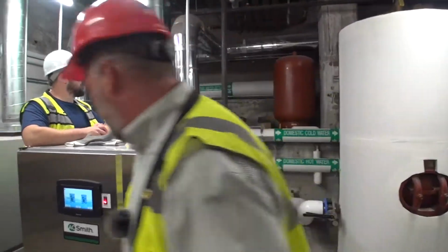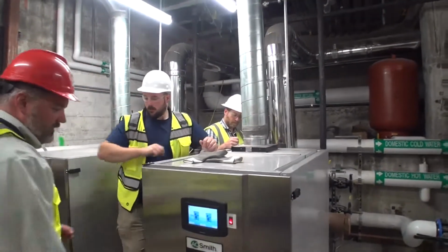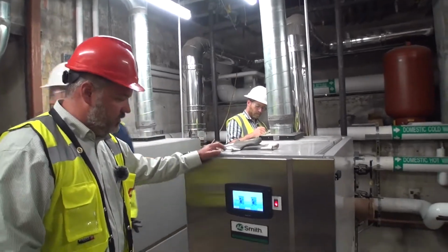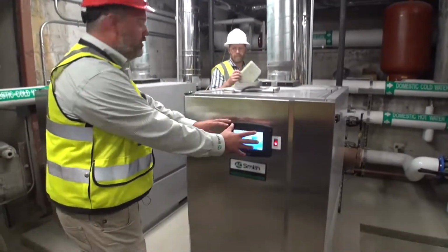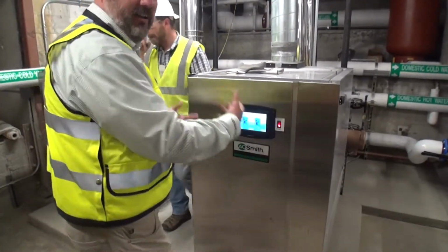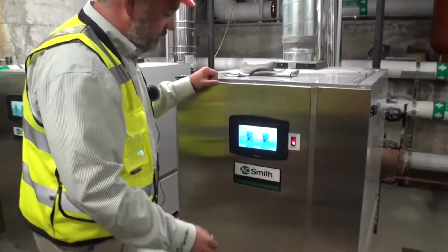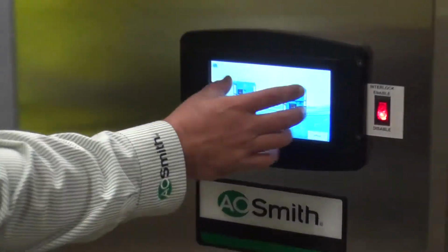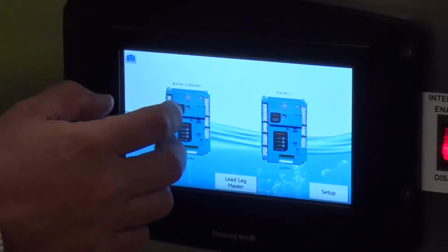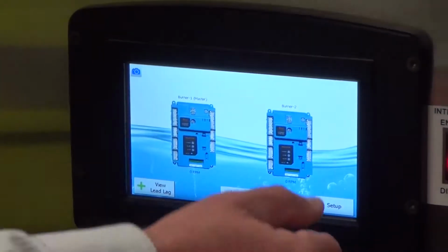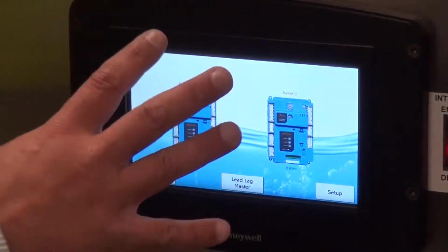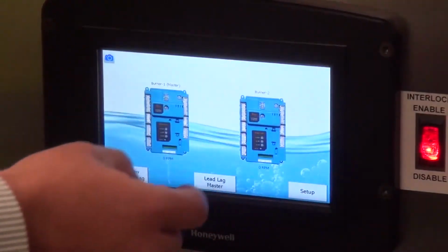All right, let's look at basic operation here real quick. I'm not sure how much people are going to get into it, but I do want to give you, we'll just do it on this one. These are the exact same controllers, exact same boilers. So we've got a boiler operation here. We've got a master burner, a 2-burner. When we open this up, there's a 2-burner setup in this unit. If there were 4 burners, you'd see 4 controllers on here.